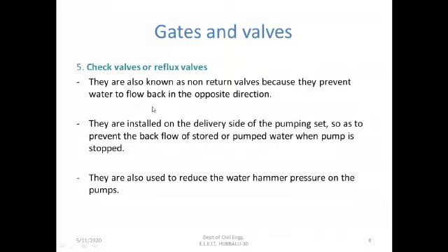Coming to the check valves or the reflux valves, these are also known as non-return valves because they prevent backflow, that is the flow in the opposite direction. Usually they are installed on the delivery side of the pumps, so as to prevent the backflow of the stored or pumped water as soon as the pump is stopped. And they are also used to reduce the water hammer pressure on the pumps. This is how they look.